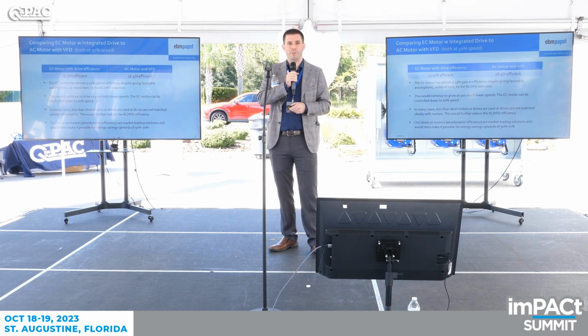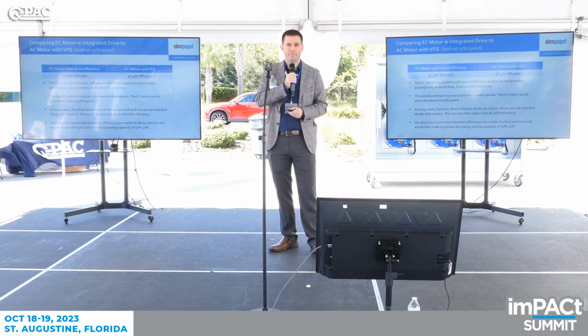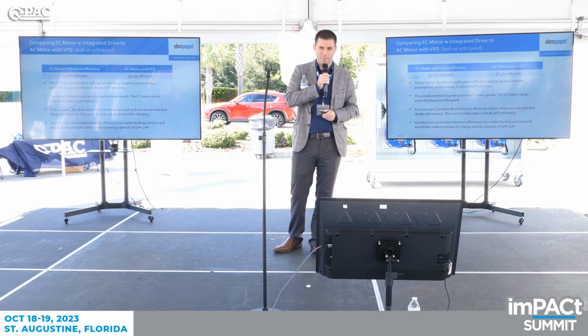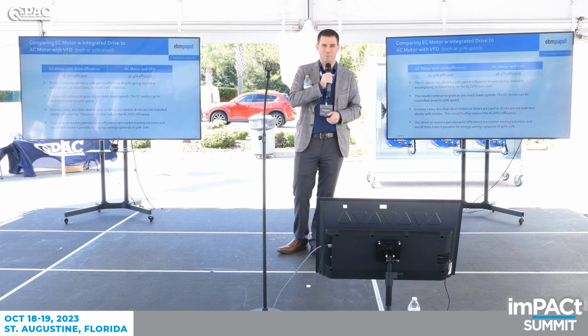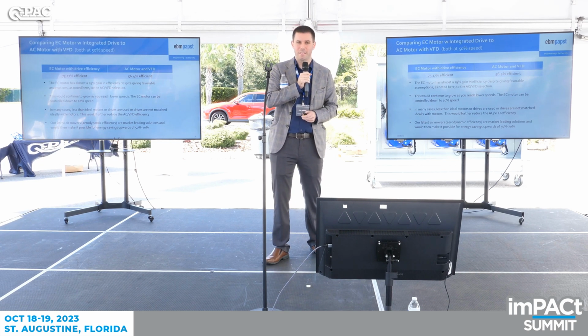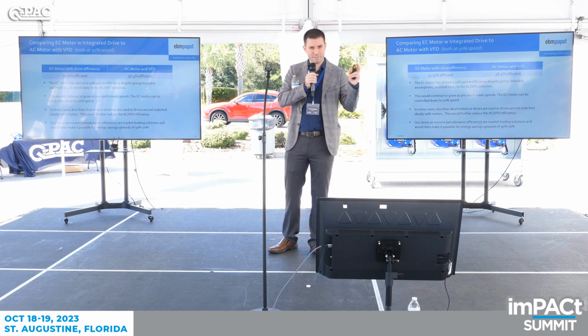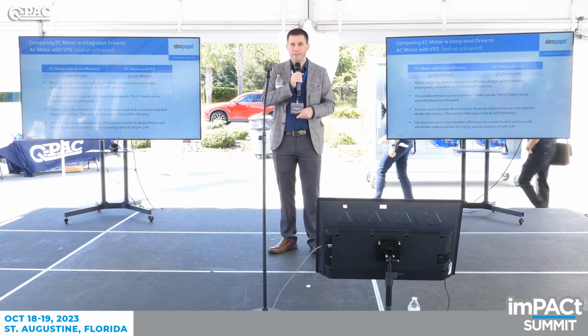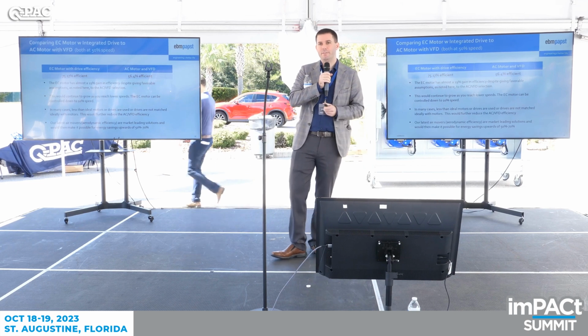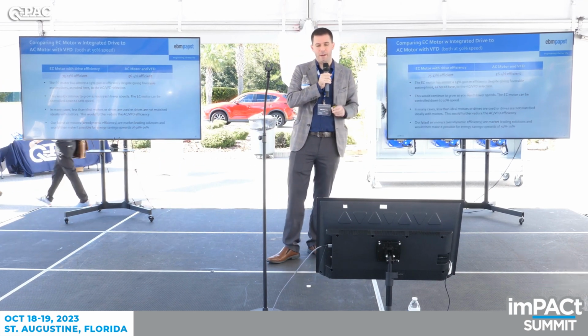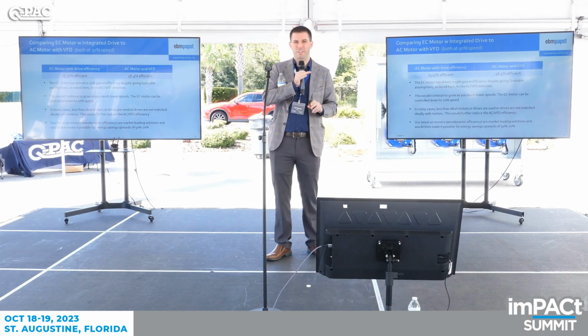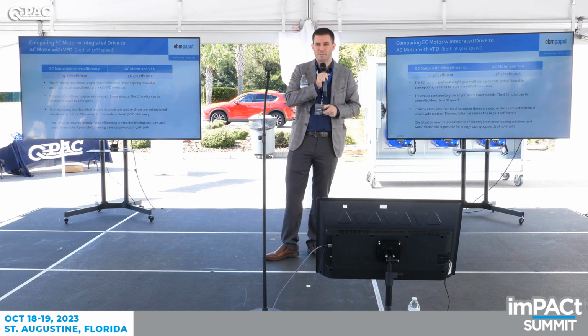Lots of times, units are designed for the hottest day of the year, and most of the time it's operating at a part load. So this is why this is so important. Most of its operating hours are not going to be at 100%. This continues to grow as you go down in speed. EC motors can get down to 10% speed, and even a little lower, actually, whereas an AC VFD, normally you're going to be around 30, 35% speed.